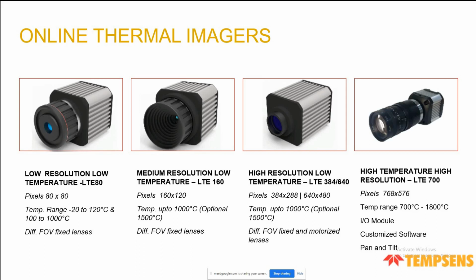We have low resolution options: 80 by 80, 160 by 120, 384 by 288, 640 by 480, and for high temperature, one covering 700 to 1800 degrees. The first three can work up to 1000 degrees centigrade and are quite suitable. Today they are replacing pyrometers in a lot of places, and they can give you much more information than pyrometers.